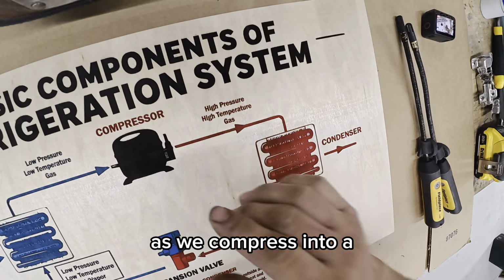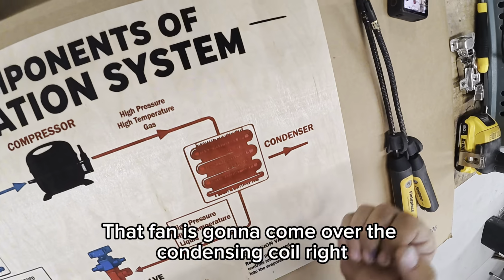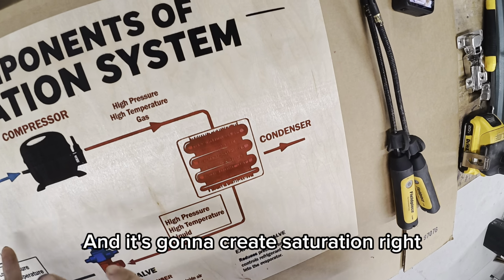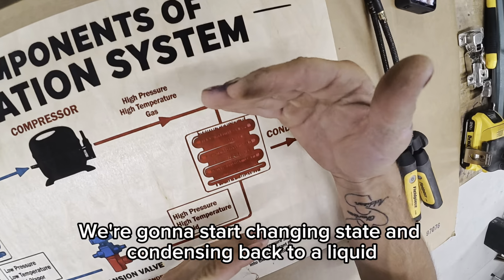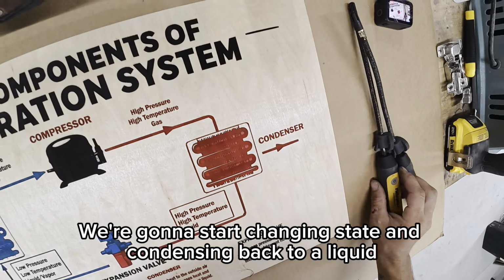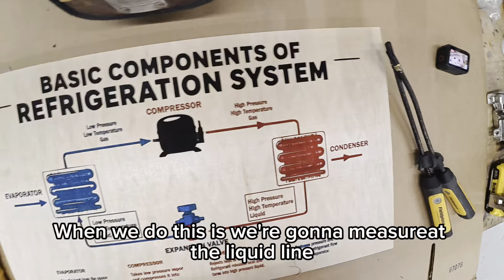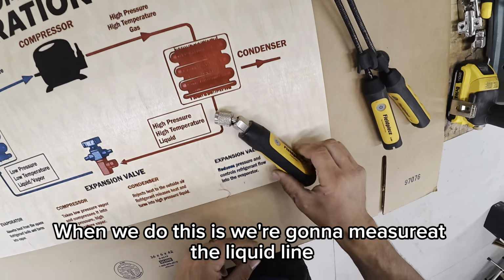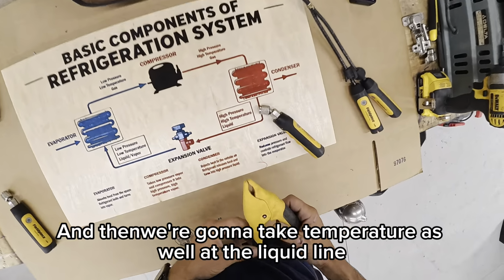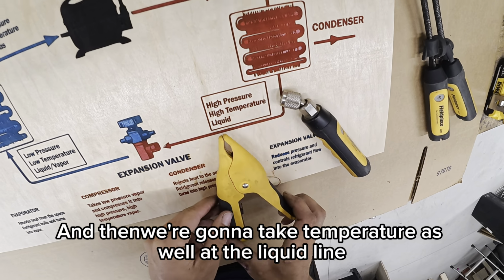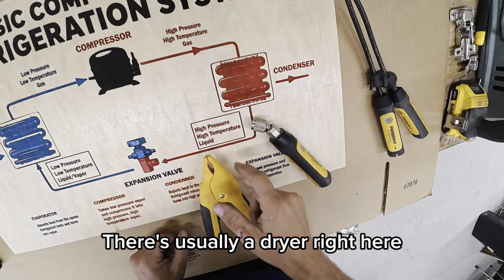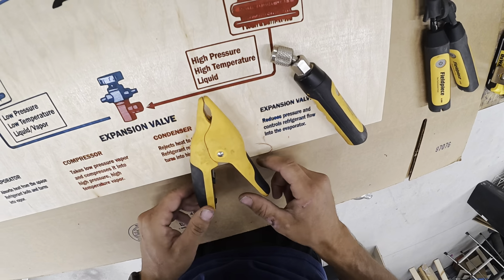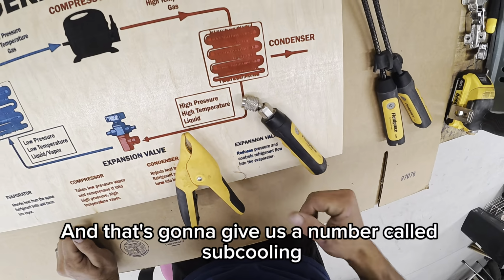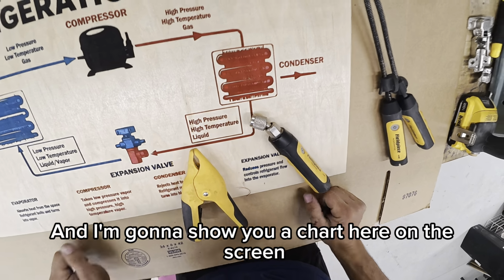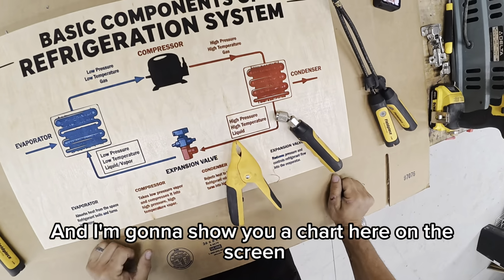As we compress into a high temperature gas and we're really hot, that fan is going to come over the condensing coil, right? It's going to create saturation, right? We're going to start changing state and condensing back to a liquid. The whole goal when we do this is we're going to measure pressure at the liquid line, and then we're going to take temperature as well at the liquid line. There's usually a dryer right here. You want to be after the dryer, but we're going to take that measurement, and that's going to give us a number called subcooling. And I'm going to show you a chart here on the screen.